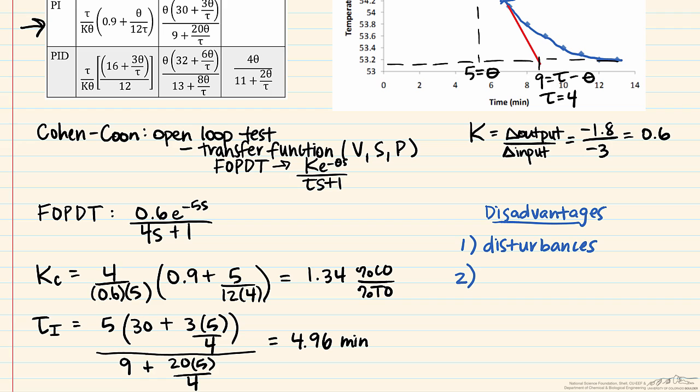Additionally the second issue is the fact that the calibration of the controller is important, and this is because we have to ensure the fact that the change in percent controller output is consistent, otherwise this could become potentially dependent on whether or not you did an increase or a decrease or where this increase or decrease occurred.